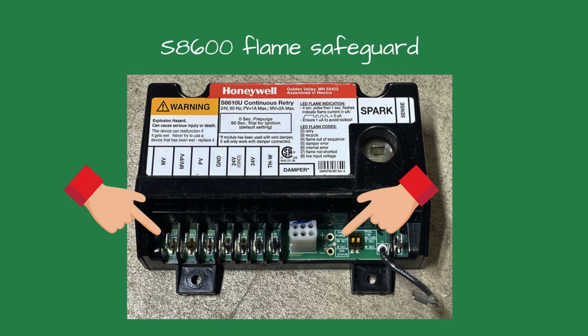For Honeywell S8600 series flame safeguards, disconnect the MV terminal from the control. Set the meter to DC microamps. Insert the probes into the flame current test holes. Measure with the pilot only, no main gas. The minimum should be 1.0 microamps DC, steady. Recommended is 2.0 microamps or higher for reliability.